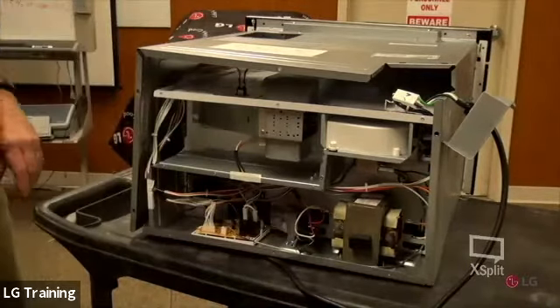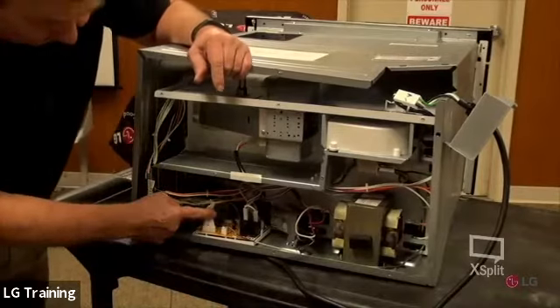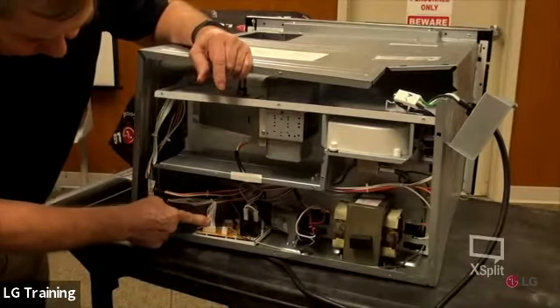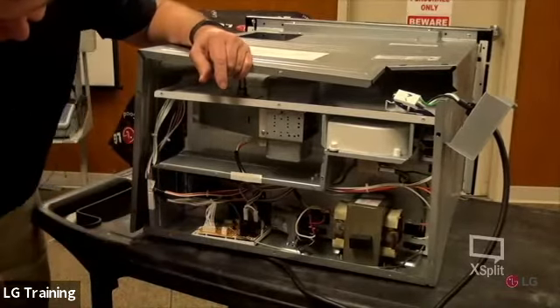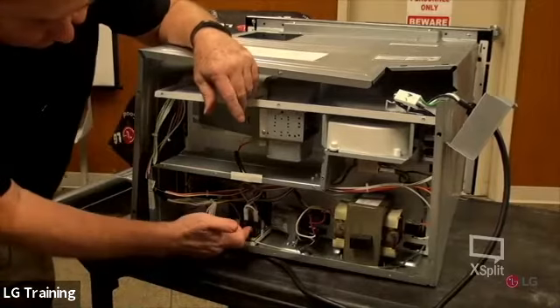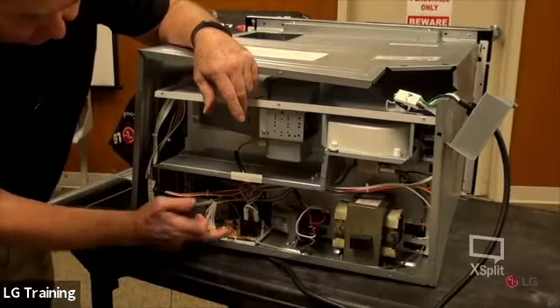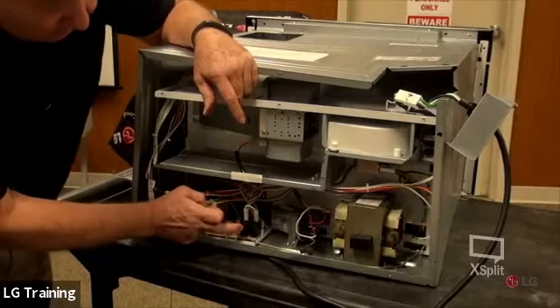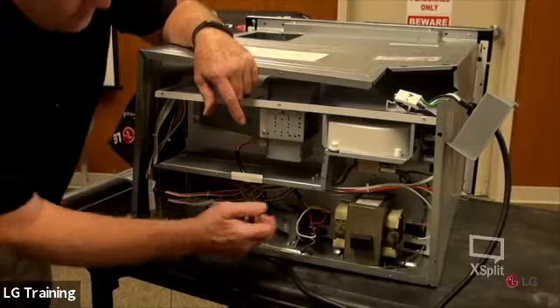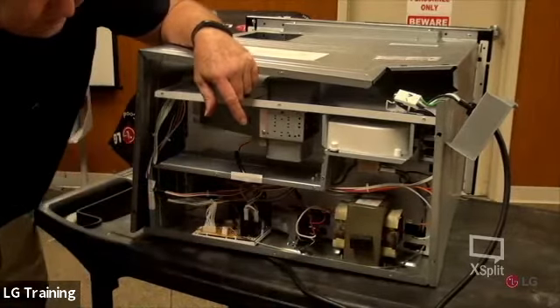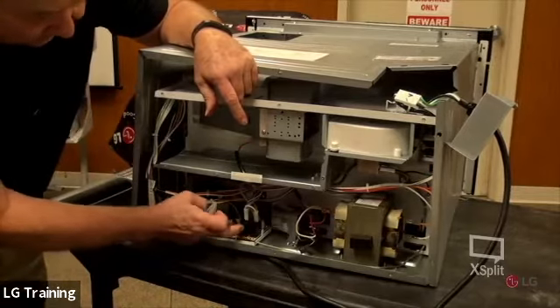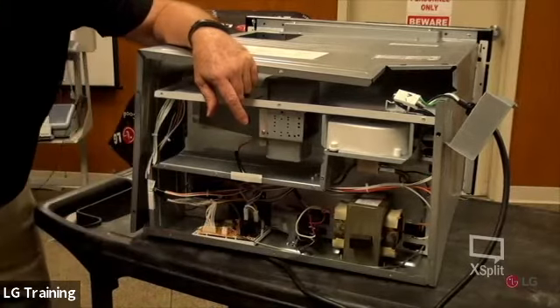All right, so here's that. They call it this power supply board - I like to refer to it as maybe a relay board. We've got these two relays here. One of these is for the lamp, and the other one is for the L1 side to the primary side of the transformer. That's the relay you check if you get a no heat complaint.